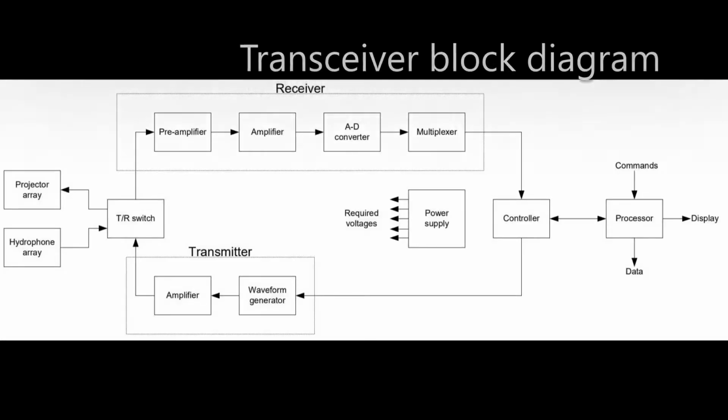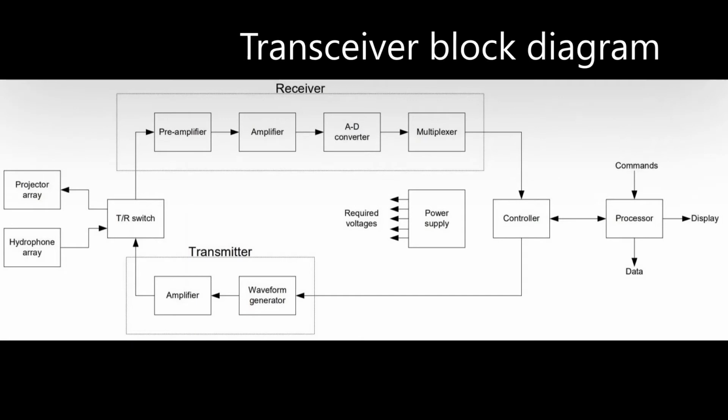Now, before we conclude our discussion, a bit on the receiver channel data. Simply stating, minute voltages are generated proportional to the incoming sound pressure level on the receiver ceramics. There are two transformations thereafter which happen. One is the digitization of the signal and the other is the application of the gain, which basically is the amplification of the signal. So these voltages are amplified and then converted to digital signals by the analog to digital converter or the ADC card. The voltage generated for each channel is then digitized.